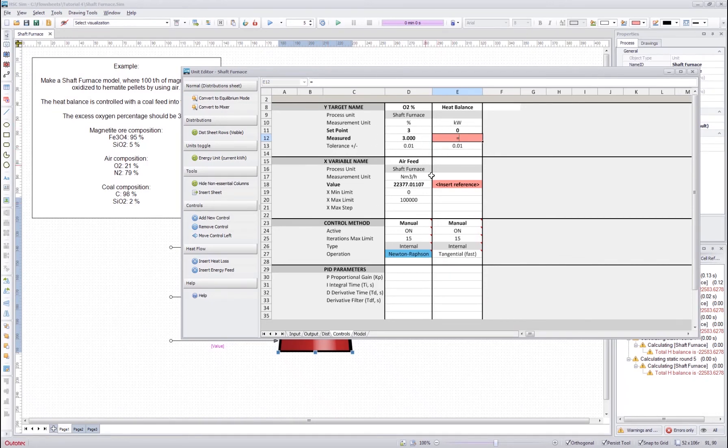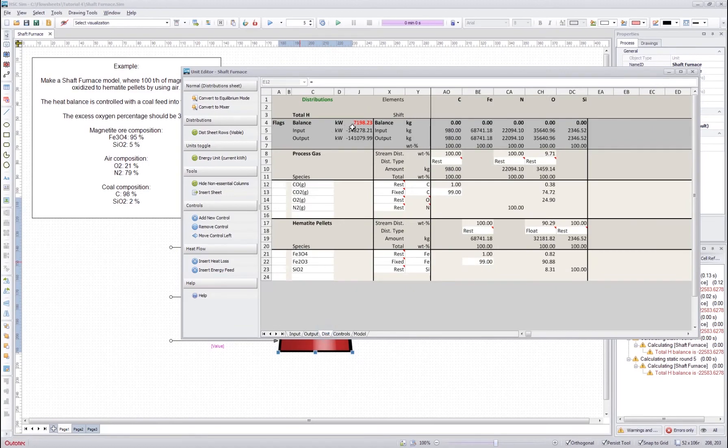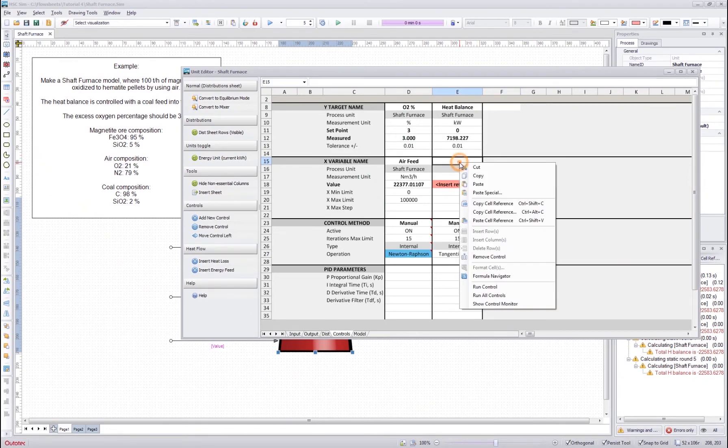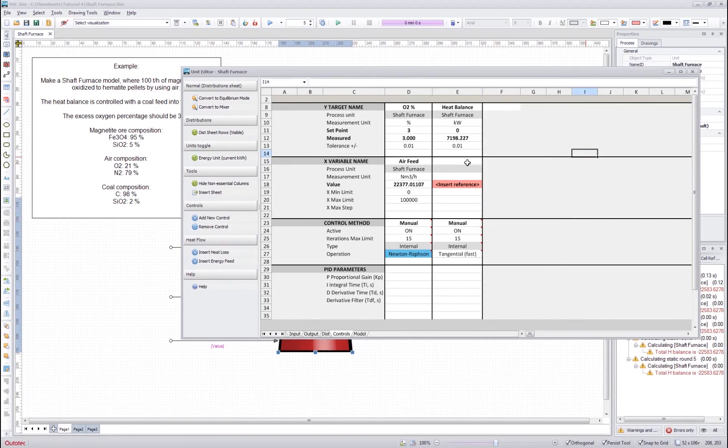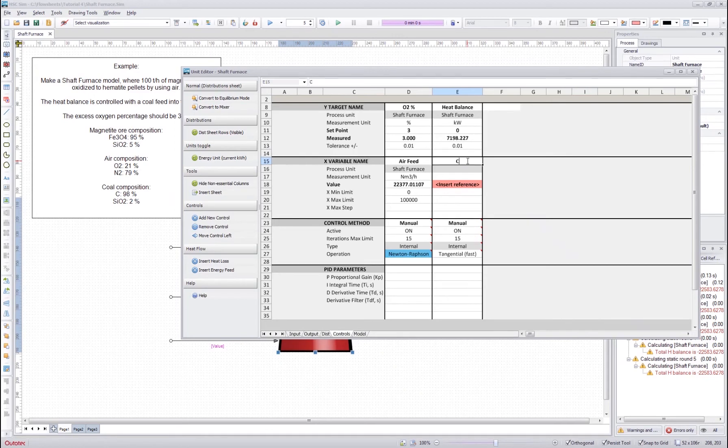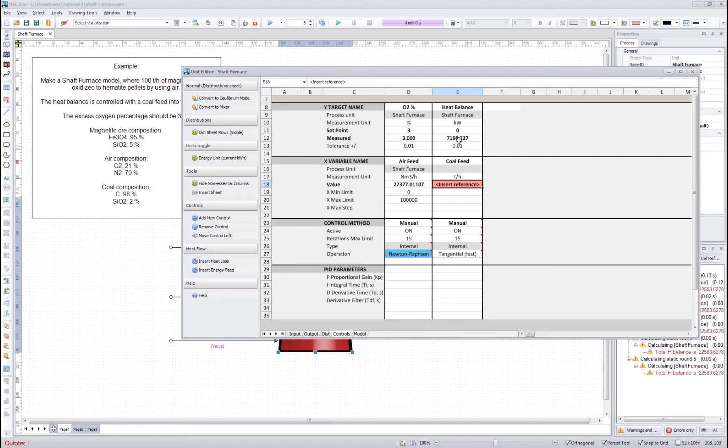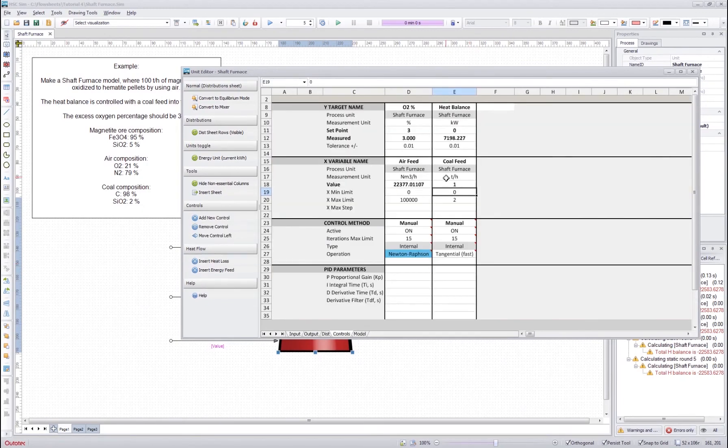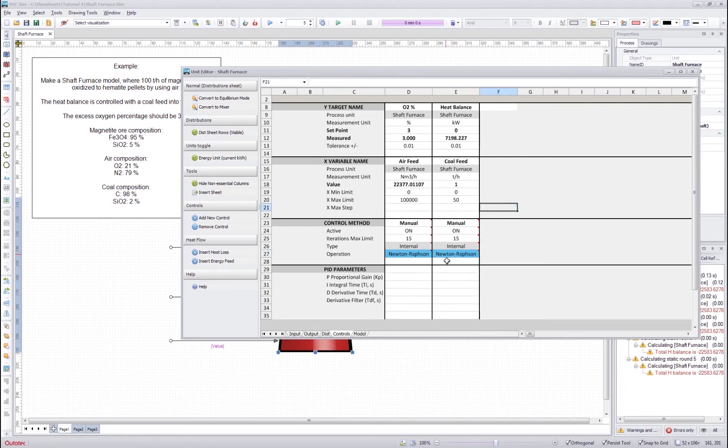And if we have this sort of internal reference, which means that it is referring to a cell inside the same unit, we can use direct Excel reference. It works the same way as copy cell reference and paste cell reference. However, if you have an external reference from another unit, then you have to use these copy and paste cell references. And then we control it with the coal feed tons per hour, and we get the reference from here. And press enter, increase the maximum, and I will use the Newton Raphson method here too.